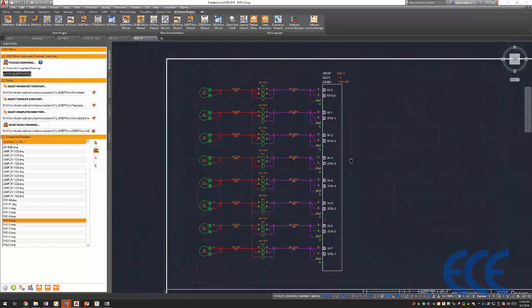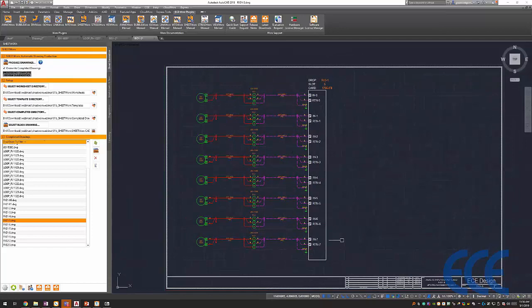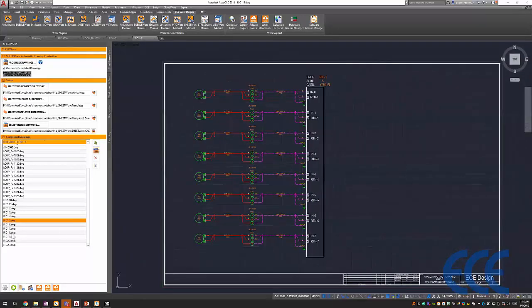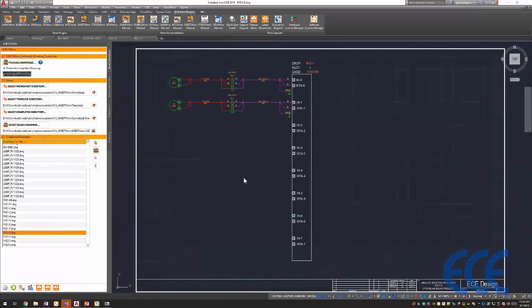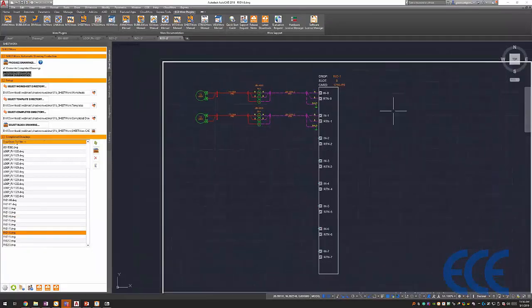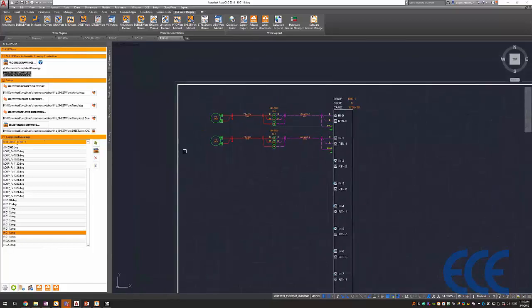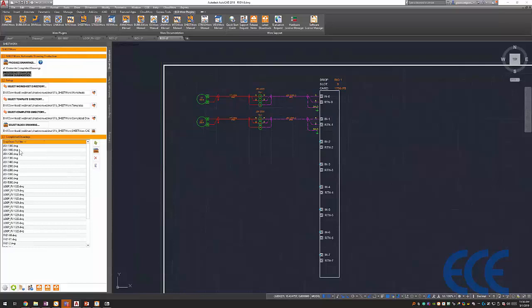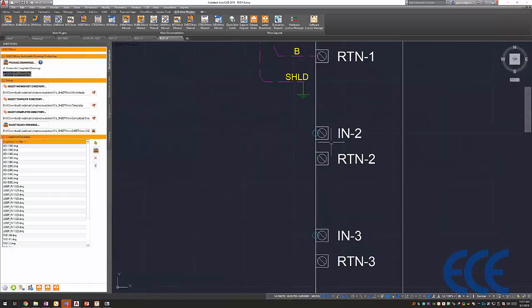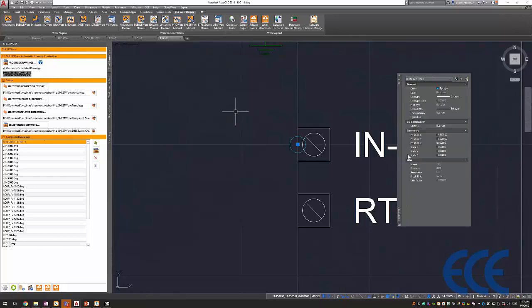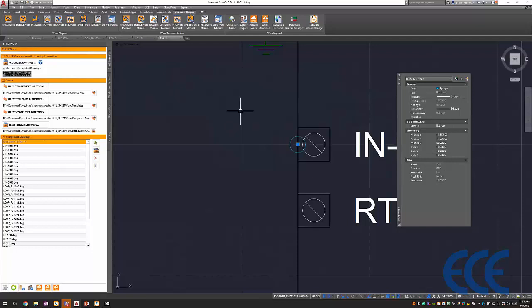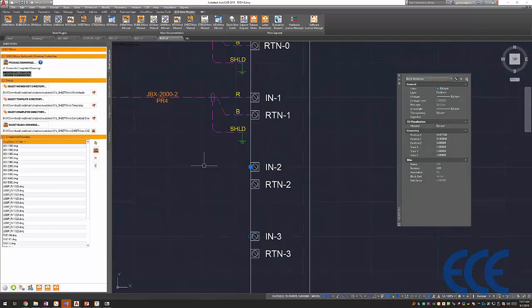Let's look at a couple different RIOs. This one is reversed. Here's the drop, remote I/O 1, Slot 5, and that's the card. So all that was also driven from Excel. And this one, I've got a couple spares here for slot 8. These blocks that I've positioned in space, there's actually a little circle in space inside CAD that was set up in the template. And what this does is it tells Sheetworks where that position is located. It's on a layer called positions that's non-plotting. So this will never show up inside a drawing if you PDF it. And it's got a name that was called out in Excel.